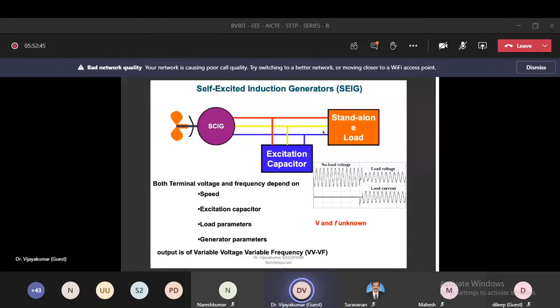So what I can say here is the voltage and frequency depend upon all the parameters, the load parameters, because the load keeps on changing. It depends upon the capacitor value, the load, the wind speed and the generator parameters. So we cannot come up with the optimum points of this.